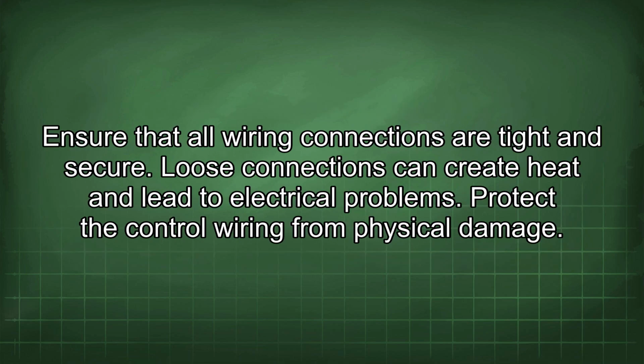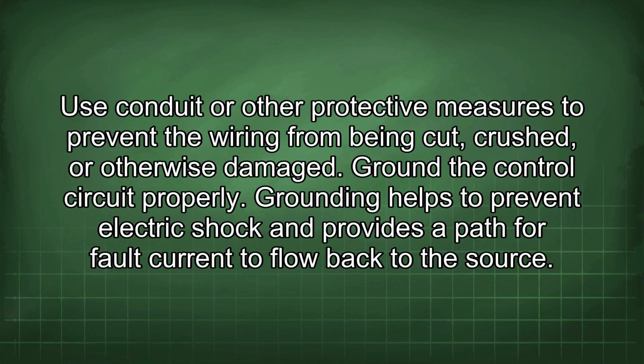Ensure that all wiring connections are tight and secure. Loose connections can create heat and lead to electrical problems. Protect the control wiring from physical damage. Use conduit or other protective measures to prevent the wiring from being cut, crushed, or otherwise damaged. Ground the control circuit properly. Grounding helps to prevent electric shock and provides a path for fault current to flow back to the source.